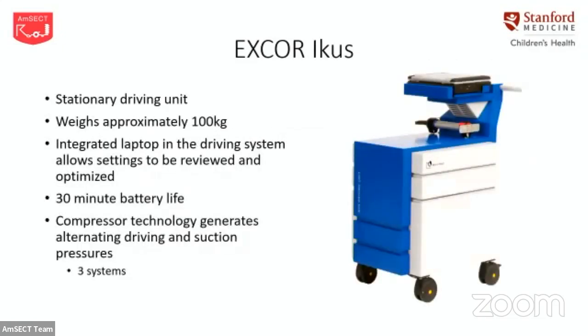And before I get into the new features of the driver, I'll do a quick review of the Ikus that hopefully most of us know and love or hate. It is the stationary driving unit that is very heavy, weighing approximately 100 kilos. There is the integrated laptop that we use to change and review our settings. There is a very short battery life of 30 minutes. And the Ikus uses compressor technology for our suction and driving pressures.